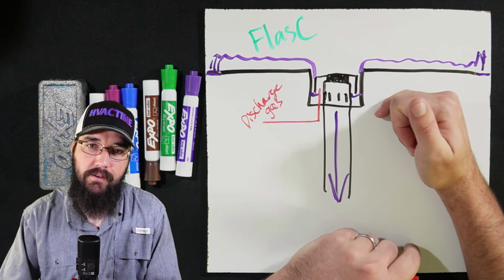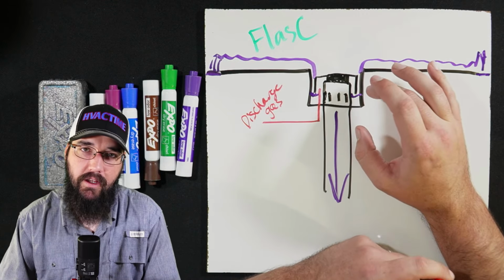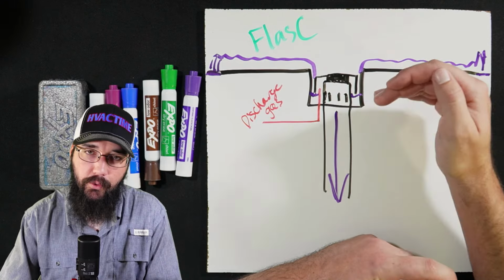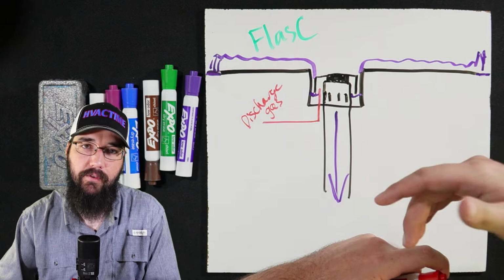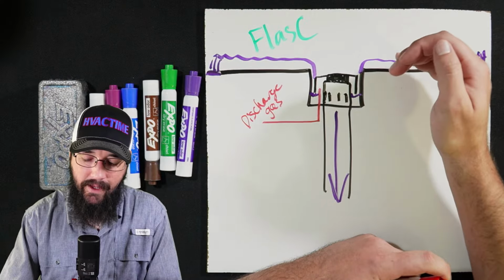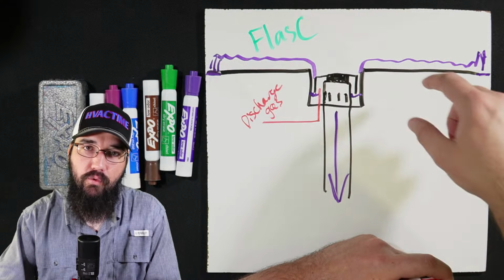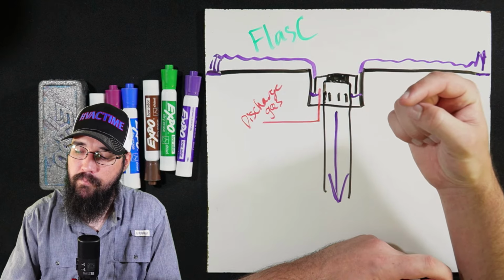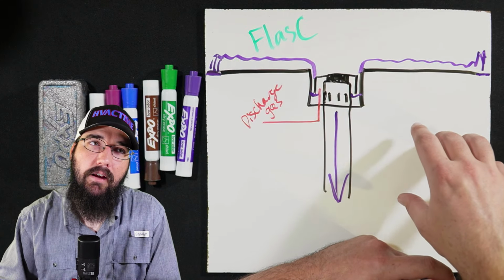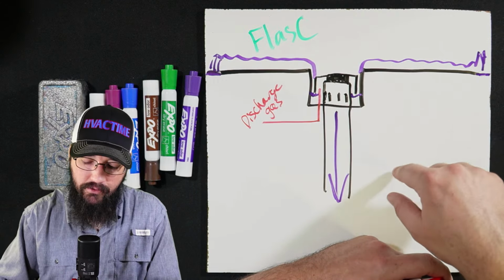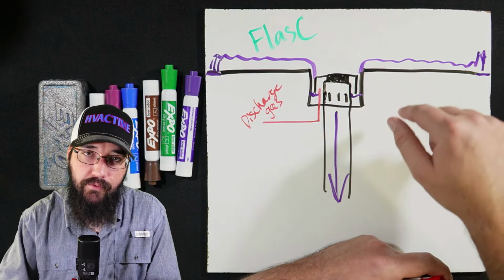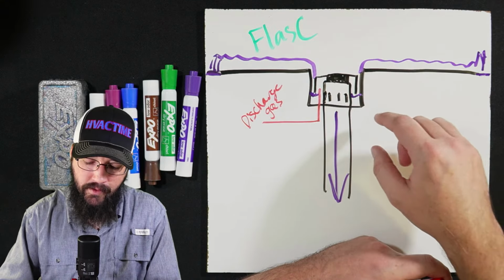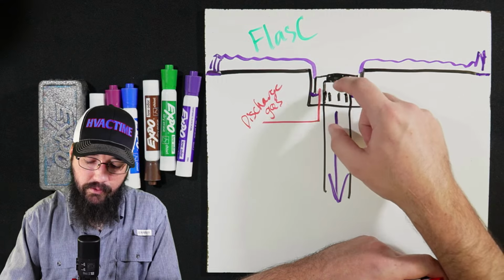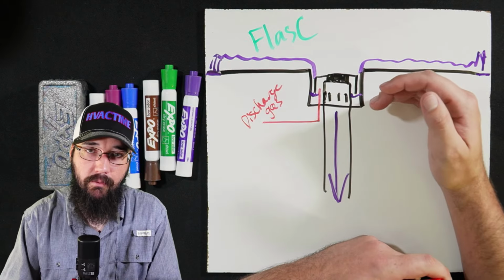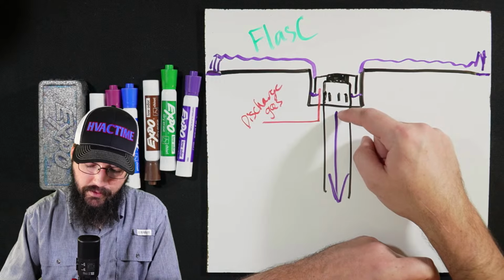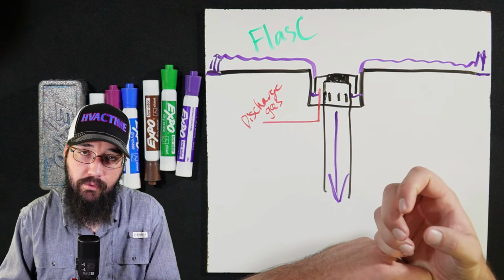So I talked about this a lot in the last stream, but something to understand with machines like this: as load increases and decreases on the machine, the compressor moves more CFM and stages up and down, if you will. That affects how much liquid level ends up getting stacked and moving through the machine, or how much total refrigerant is actually cycling at a given time, right? So the higher the machine loads up and stages, the more refrigerant it's physically moving, which does result in higher levels here. So as we have more load on the machine, more liquid is getting into here. This valve opens up because of higher liquid levels, because we're moving more refrigerant in total, which then allows us to feed more into the evaporator, which is getting more suction pulled on it because of the higher load.